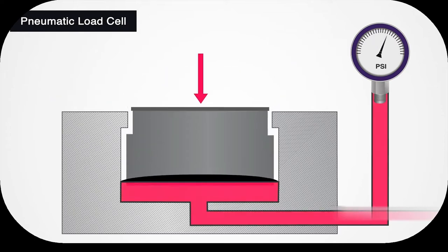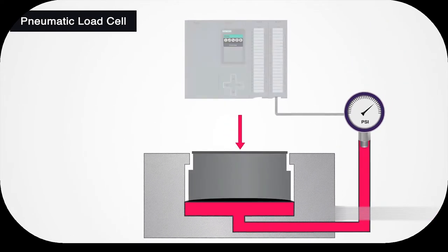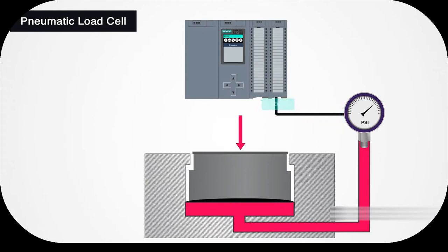When a load is placed on the loading platform, the piston applies pressure to the liquid contained inside it. The pressure increase of the liquid is proportional to the applied force or weight. After calibrating the pressure, you can accurately measure the force or weight. The pressure reading can be read as an analog gauge or converted into an electrical signal from a pressure sensor.